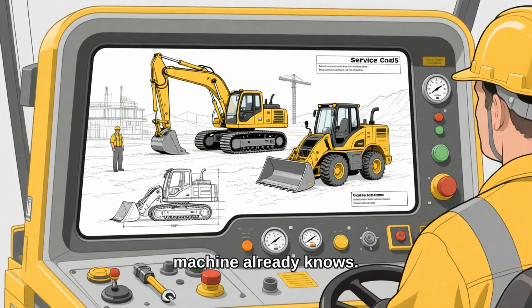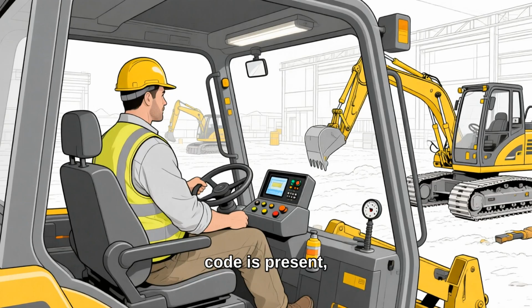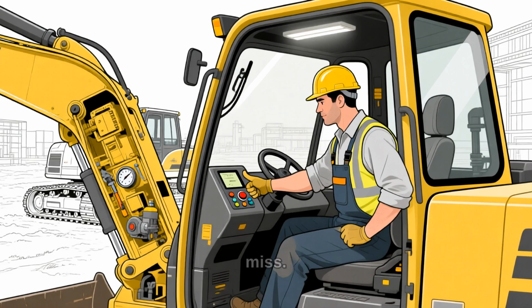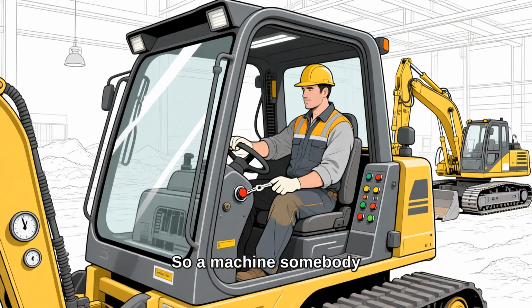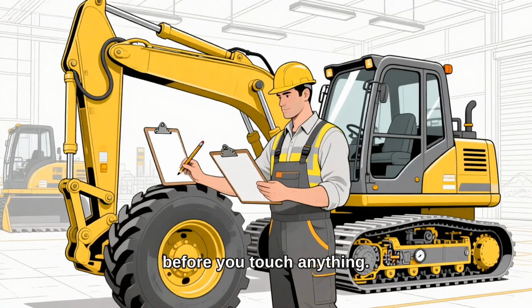Start with what the machine already knows. The display panel holds service codes on its own code screen. If more than one code is present, they scroll. You end up watching them cycle instead of reading a list. Here's the part people miss. The newest code sits in position 1, and as new ones arrive, the oldest disappears. So a machine somebody cranked 20 times before you arrived may have already erased the first clue. Write every code down before you touch anything. That list is evidence, and it's quietly expiring.